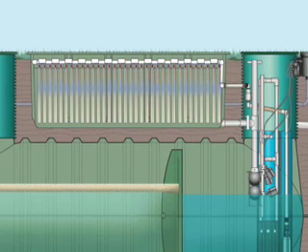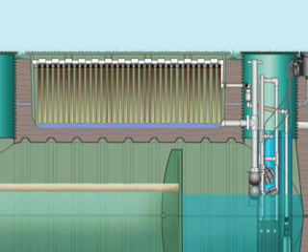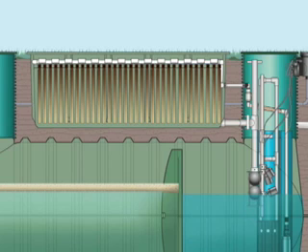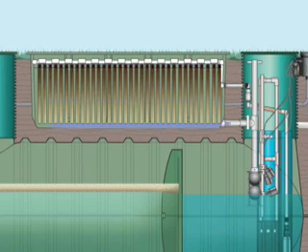In the pod, effluent percolates down through the textile media and is collected in the bottom of the pod. This effluent flows to the recirculating splitter valve. After circulating through the system repeatedly, the treated effluent is eventually discharged to the dispersal area.